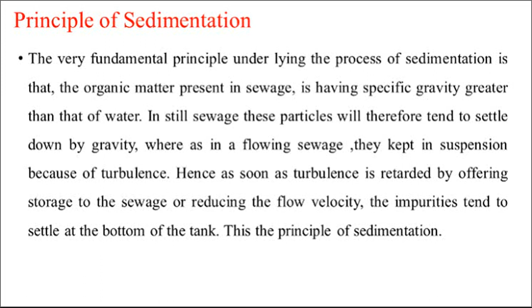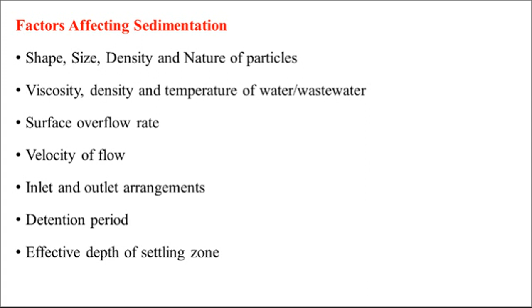Next, factors affecting sedimentation. There are various factors on which the efficiency of sedimentation depends. First one, shape, size, density and nature of particles or impurities present in wastewater. Second factor, viscosity, density and temperature of wastewater. Then surface overflow rate applied on a particular sedimentation tank. Then velocity of flow. Depending upon the velocity of flow or horizontal velocity, the sedimentation efficiency increases or decreases. Then inlet and outlet arrangement, detention period, and effective depth of settling. On all these factors, the efficiency of sedimentation of a particular tank will depend.